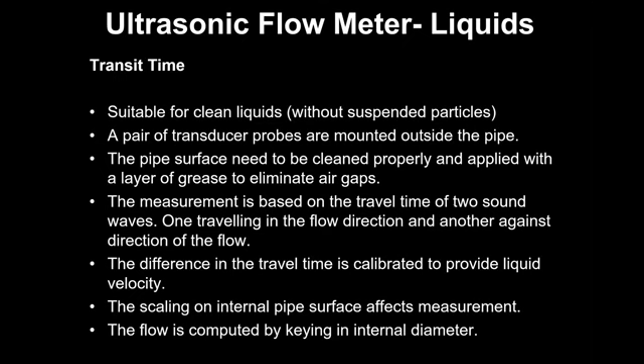If the signal is not received, you can still adjust the distance between the two probes, because what the instrument gives is slightly indicative. So you can adjust the transducer distance so that the signal is appropriate as per the requirement of the instrument, and based on that, you can get the flow rate. The instrument will tell you whether the reading is correct or not, whether you're getting the reading or not. But as I said in the beginning, it will not tell you if there is an eddy current inside. If you don't select the straight length properly, it is not going to tell you that you have not selected the straight length. But if the probe distance is not correct or the signal is not received properly, all that will be indicated by the instrument. To that extent, these instruments are good. They will help you. There are a lot of functions available with which the reading can be correctly obtained. But other things we need to be careful about.